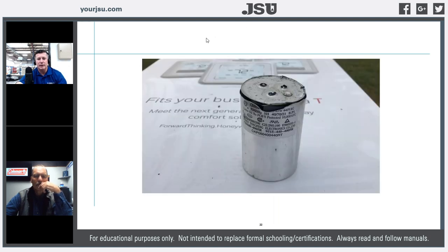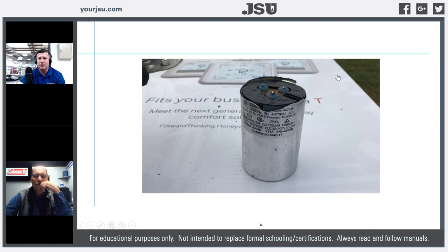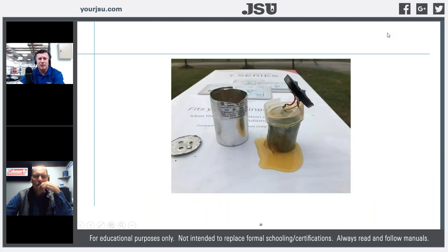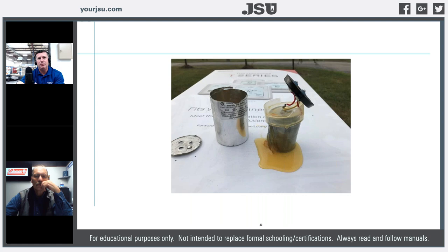We cut it open to understand how it's constructed so we can better diagnose what has failed. When you go to the top end and see it melted, it couldn't handle the voltage running through it — heat created by the voltage melted it internally. The hottest part is the center of the core. As technicians with 21 years in the field, we'd never cut open a capacitor. Understanding the construction of something helps you understand how it's affected and what fails inside.